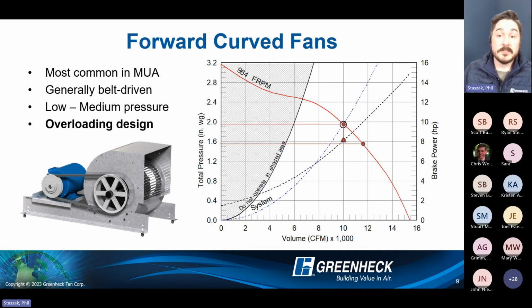Real world scenario though is, all right, we calculated for a 1/2 inch of static pressure that actually doesn't exist. So now we set that unit out on our rooftop, and naturally we're going to move more airflow than what was originally laid out or designed, because it was laid out around 10,000 CFM. It doesn't have that resistance to overcome on the other end. So now we're moving closer to 12,000 CFM. And with a traditional forward curve fan, it is an overloading design. So now we trace that up and we're moving more airflow and we're right at that 10 horsepower.